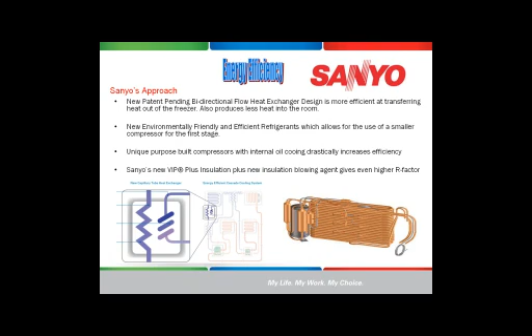To look at energy efficiency, for the purposes of today's presentation, I'm showing how we compare to ourselves. From freezers we made just a few years ago, we are producing freezers now that have even greater uniformity, better energy consumption specifications, and allow us to bring our energy consumption on our freezers way down while still being able to increase the performance. For example, our flagship freezer, which is called the MDFU 76VC, uses 36% less power than our freezers in the past, and our smaller unit, the 18.3 cubic foot freezer, uses 47% less power. And the way we've been able to do that is a combination of, as I mentioned, the refrigerants and the heat exchanger designs in the freezer.